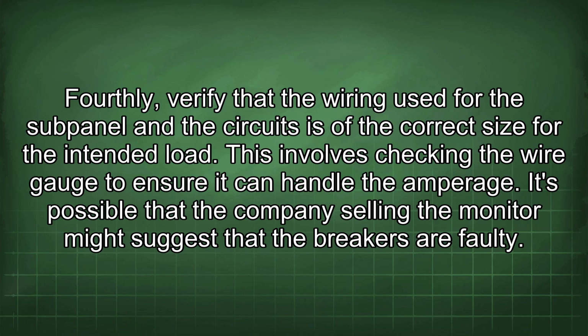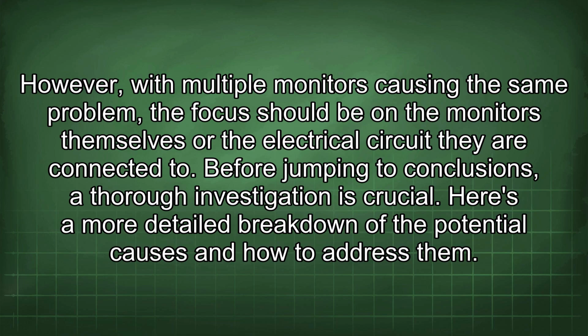It's possible that the company selling the monitor might suggest that the breakers are faulty. However, with multiple monitors causing the same problem, the focus should be on the monitors themselves or the electrical circuit they are connected to. Before jumping to conclusions, a thorough investigation is crucial. Here's a more detailed breakdown of the potential causes and how to address them.